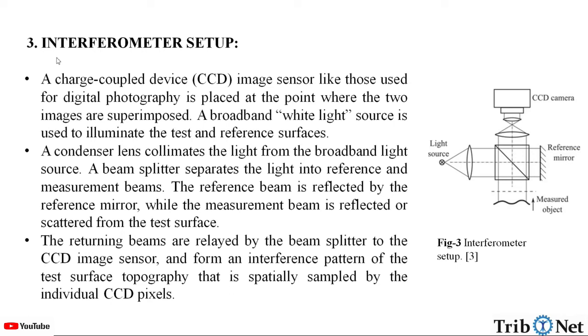The interferometer setup consists of a charge coupled device — a CCD image sensor, like those used for digital photography — which is placed at the point where the two images are superimposed. A broadband white light source is used to illuminate the test and the reference surfaces. A condenser lens collimates the light from the broadband light source. A beam splitter separates the light into the reference and measurement beams.